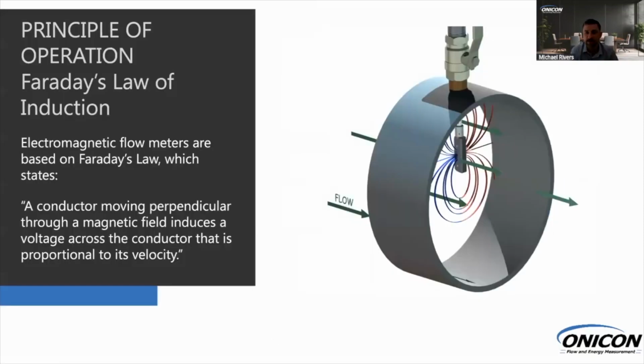How do insertion mag meters work? If you remember physics class with Faraday's law, if you create a magnetic field and put a conductor through that magnetic field, in this case water, it's going to induce a voltage. So what we're doing is measuring that induced voltage, and that's proportional to the velocity going through the pipe.